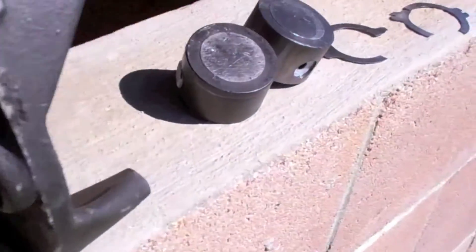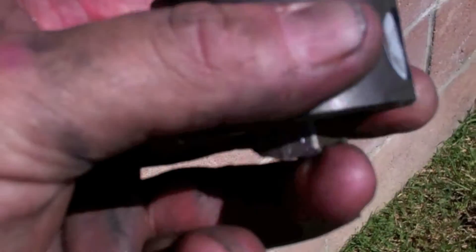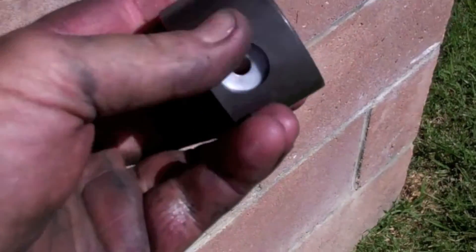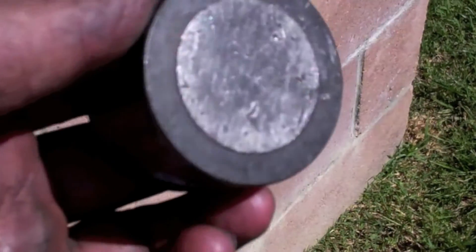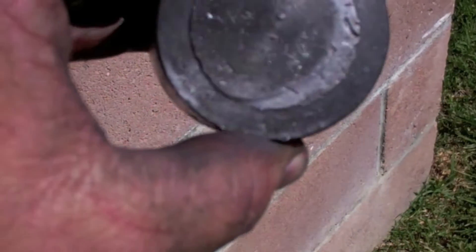Here's some of the pieces, the pistons. And you can see they show signs of wear. This one's not too bad, but this one over here, the top of the tops, the tops have just been really pitted, hammered, because the valves broke due to liquid refrigerant.